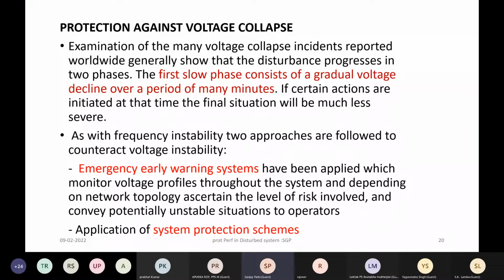Now, this type of system disturbance does not happen suddenly. Experience suggests that there is a first slow phase of the disturbance when the gradual voltage decline will start happening, and it may take minutes for this overload. As I said, for the PV curve where the nose point is to be reached, it will take some minutes, because slowly, progressively, the voltage will start going down. More reactive power will be drawn by the load. Again, voltage may go down further, and again, it's like a vicious circle. So this may happen gradually. It's not something that happens within seconds. So we should see what actions can be initiated when such a phenomenon takes place.